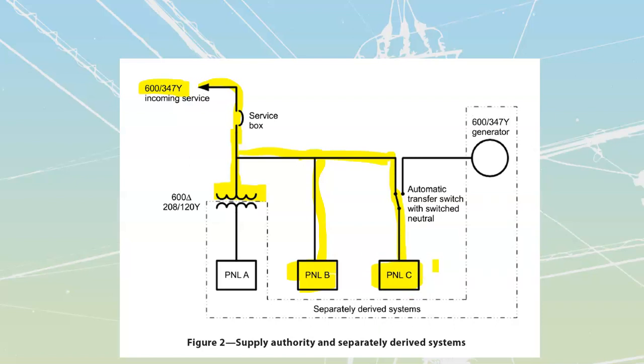What I then see is that I've also got this other definition for what we are going to refer to as being a separately derived system. Solidly grounded separately derived system is going to be any type of voltage system other than what was brought in, so 600, 347, so anything other than that was brought in that is created by the user. And it can be created through a number of things.